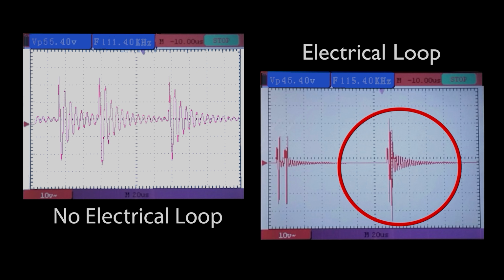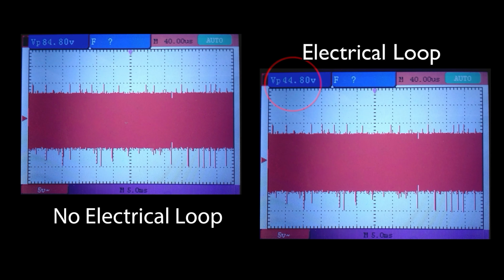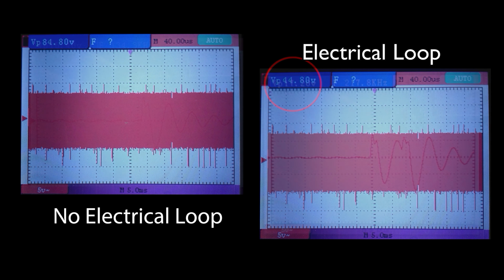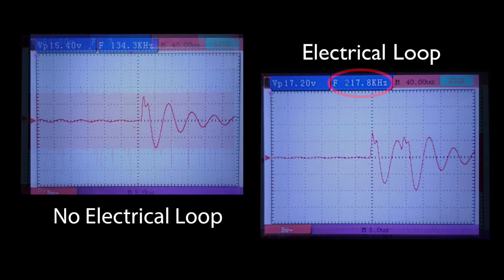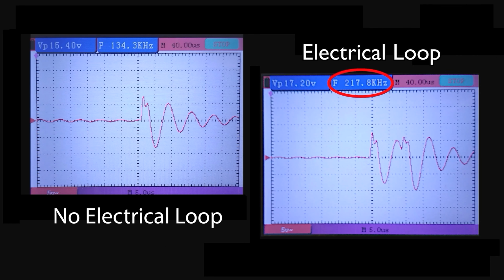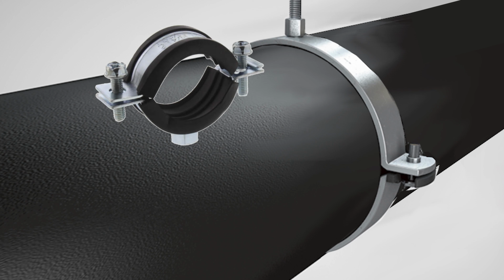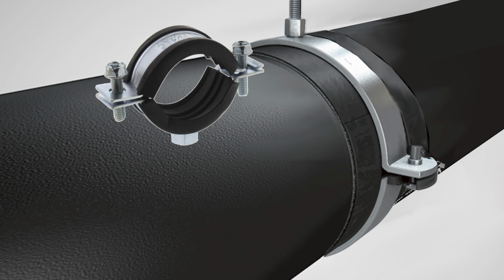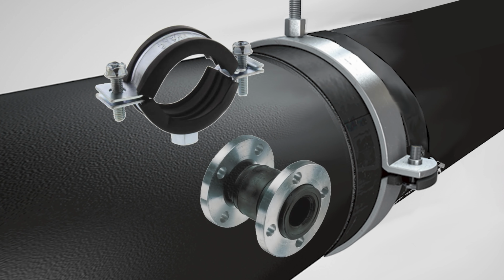If the signal resembles the one on the right, or if the peak-to-peak voltage drops by 30% or more, or if the frequency is over 200 kHz, the unit is in an electrical loop. If the unit is in a loop, it will need to be repositioned, or pipe hangers will need to be insulated, or a rubber expansion joint will need to be added.